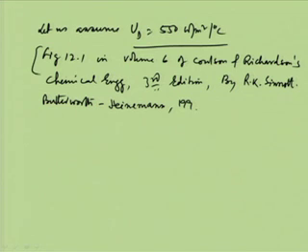So, we can find out from the figure that for this kind of process fluids an approximate value of UD is 550.